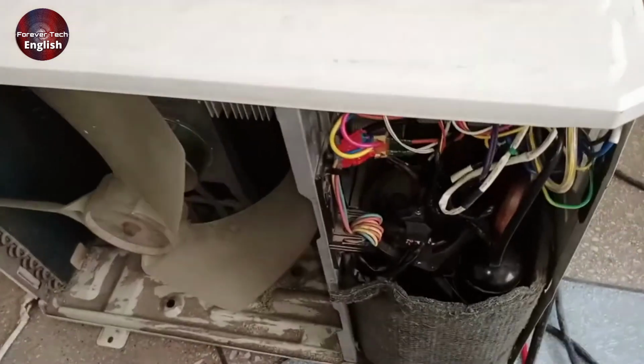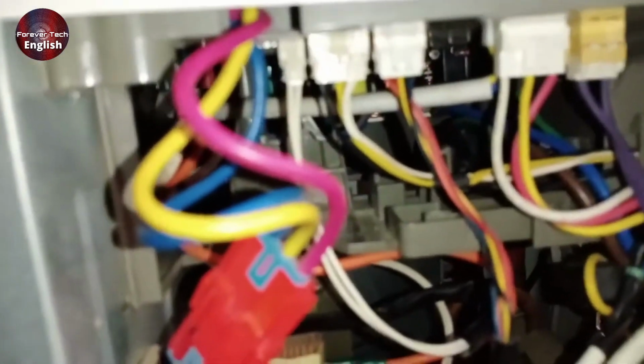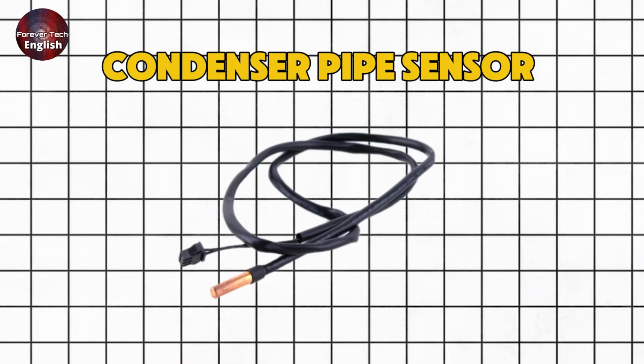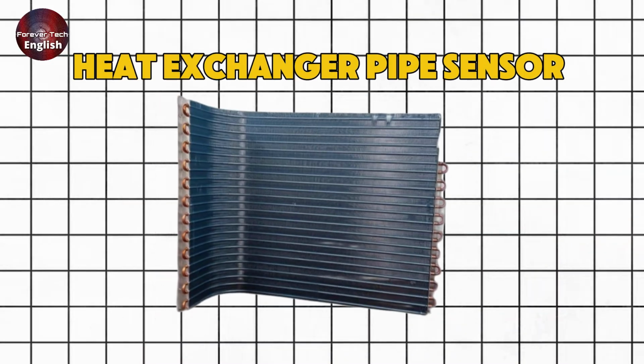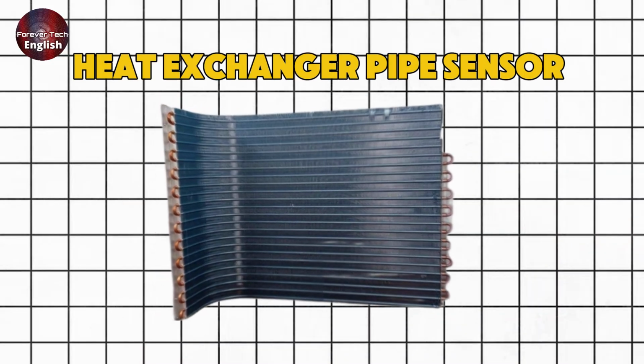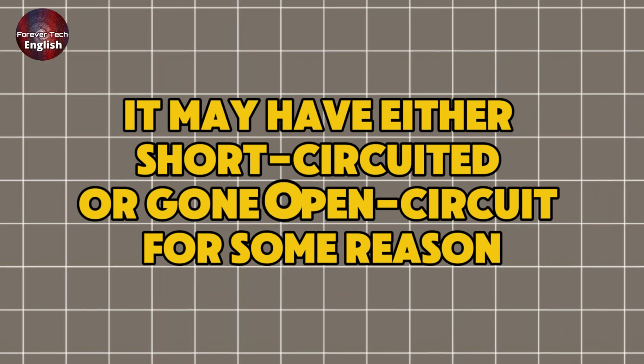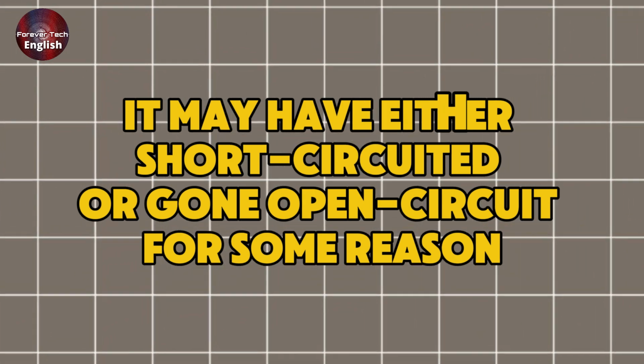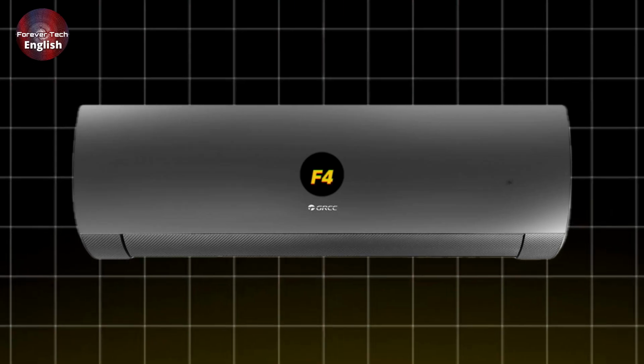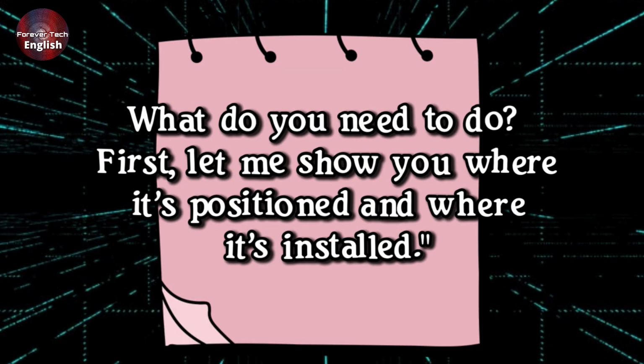Here, you can see that I've come to the outdoor unit. So whenever the F4 error code appears on the indoor display, it means that the condenser pipe sensor or heat exchanger pipe sensor in the outdoor unit has become faulty. It may have either short-circuited or gone open circuit for some reason, which causes this error code to show on the display. To fix this, what do you need to do?